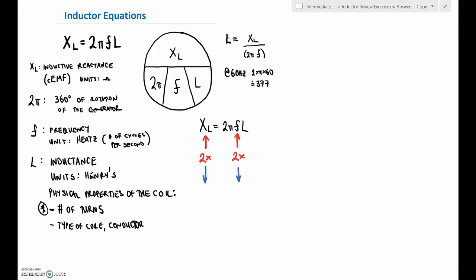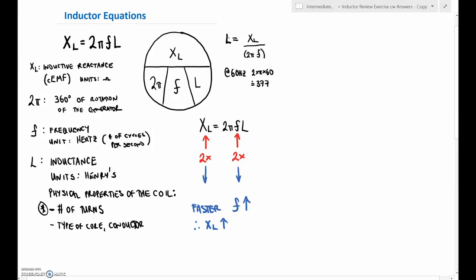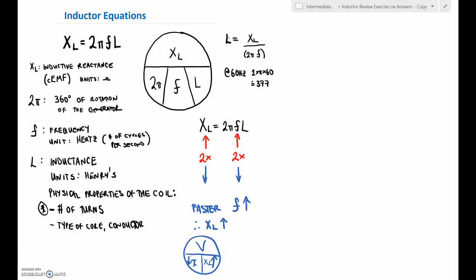A variable frequency drive changes the frequency to make a motor go faster or slower. If the frequency goes up, XL goes up by the same amount. Looking at Ohm's law with constant voltage, if XL goes up, current goes down. That's a problem — if we make the motor go faster but lose current, we lose torque, because torque is based on the magnetic fields.